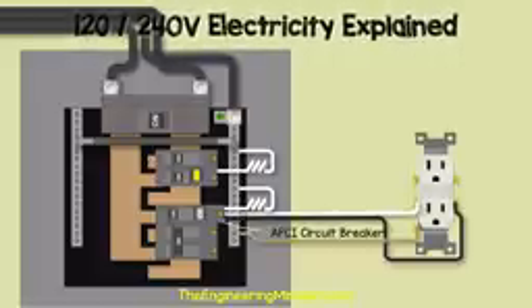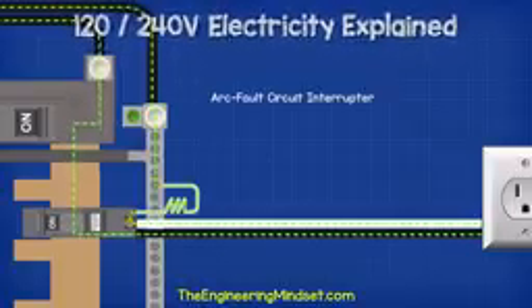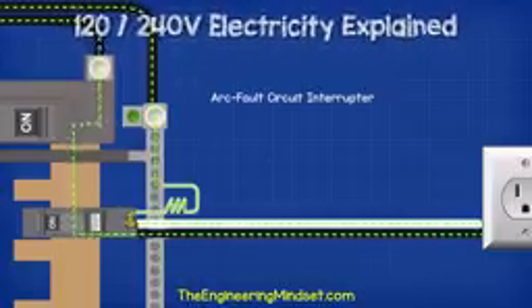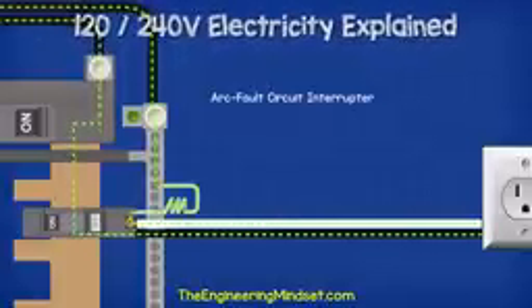We might also come across an AFCI circuit breaker. This stands for Arc Fault Circuit Interrupter. These are required for circuits feeding bedrooms, hallways, kitchens, etc. Again, check with the National Electric Code for exact details. AFCIs work also by being connected to both the hot and neutral wires. Inside this circuit breaker is a circuit board which is measuring the circuit and monitoring for patterns which indicate an arc fault is occurring. These are installed pretty much identically to how we saw the GFCI breaker. Under normal conditions, the current flows through the hot, back through the neutral into the breaker, then through the pigtail and back through the neutral bar.